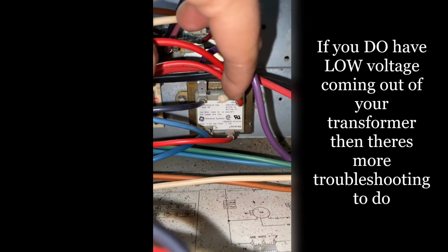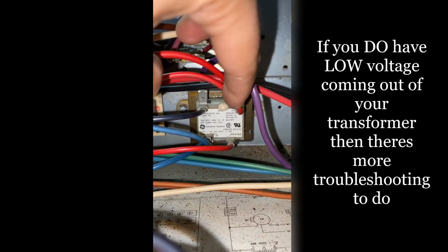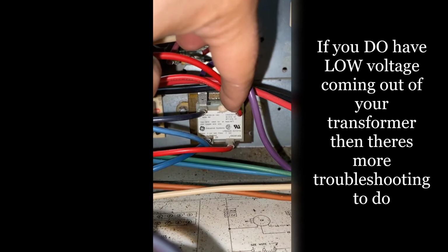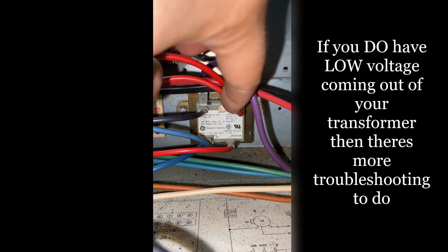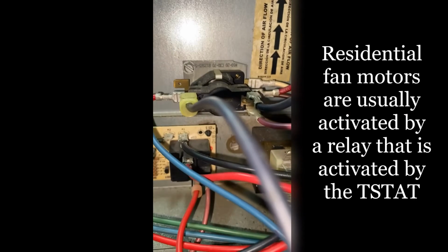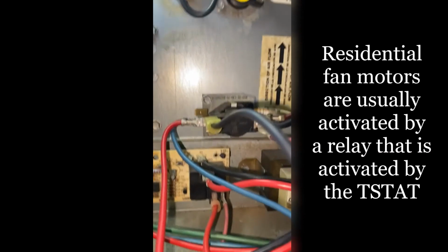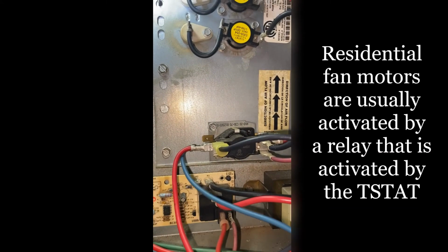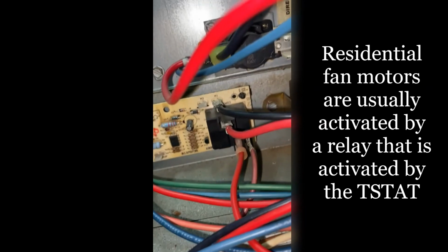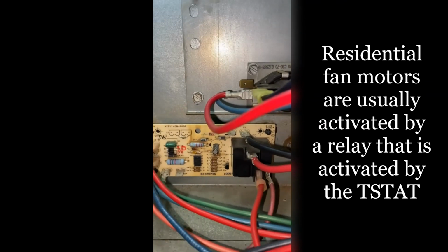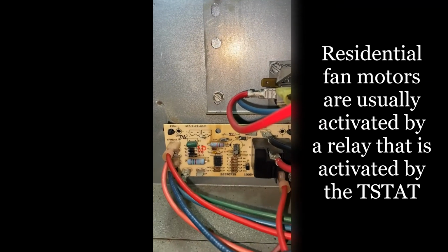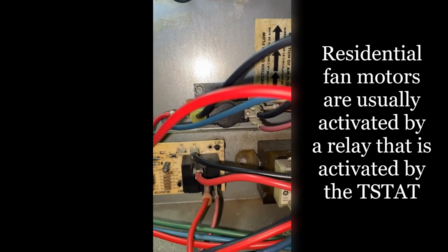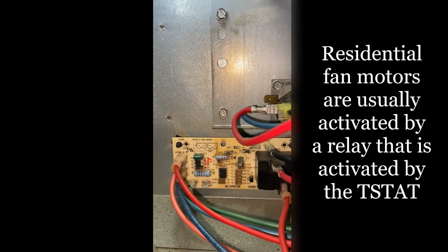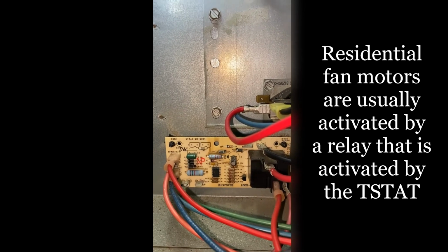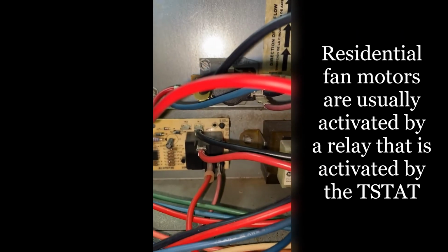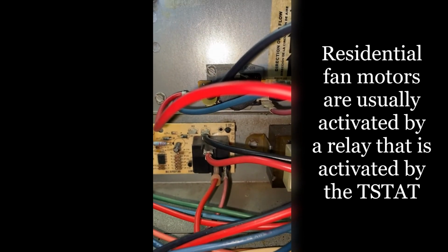So if you checked and you have high voltage coming into the transformer and low voltage coming out of the transformer, then your problem is not here. You've got to keep going. Most fans are activated by the thermostat, which activates a relay. Here's our relay here. It happens to be on a board. Sometimes you just have a relay, but this one has a board with the little relay on it. It's still the same thing. The board just does other things, like speed and stuff like that. But in reality, all you're doing is applying power through this relay.